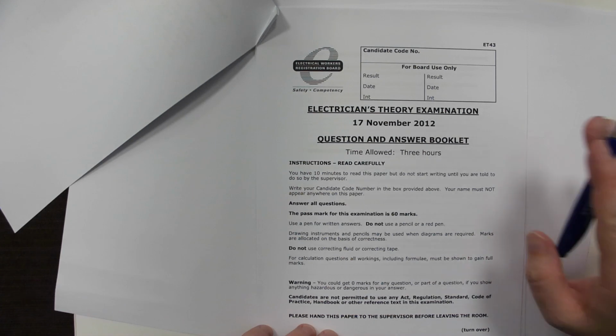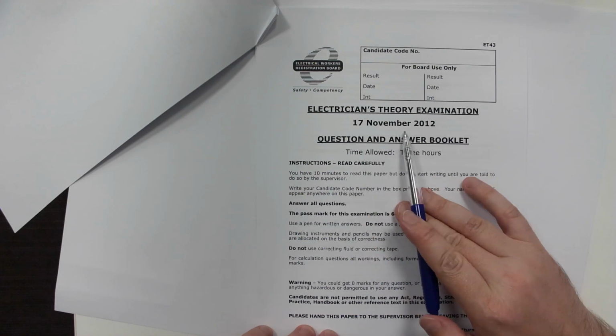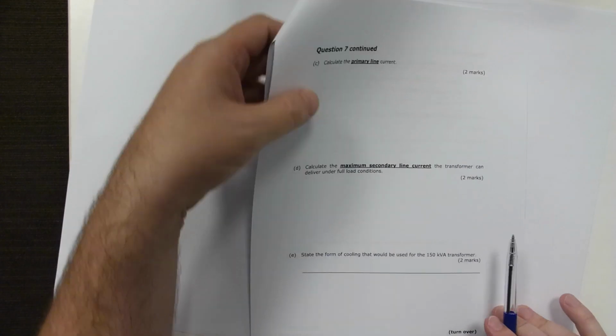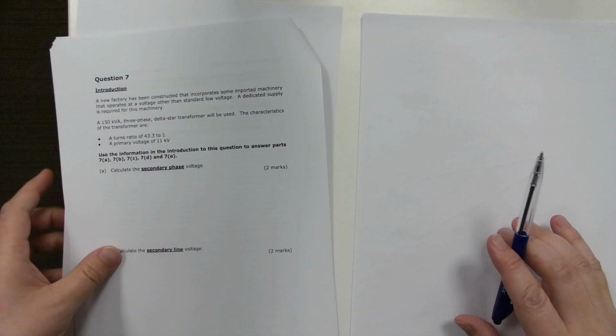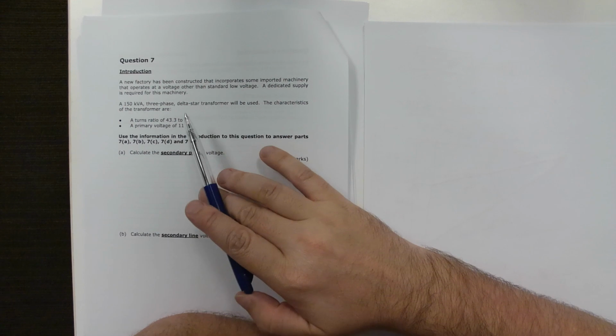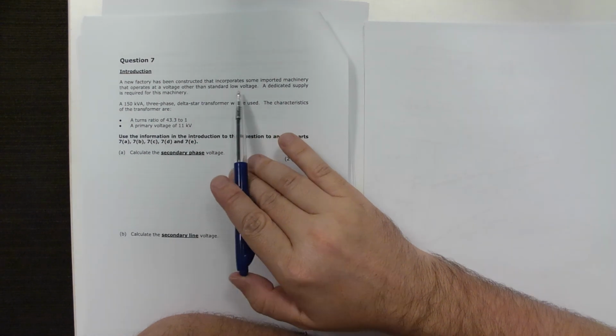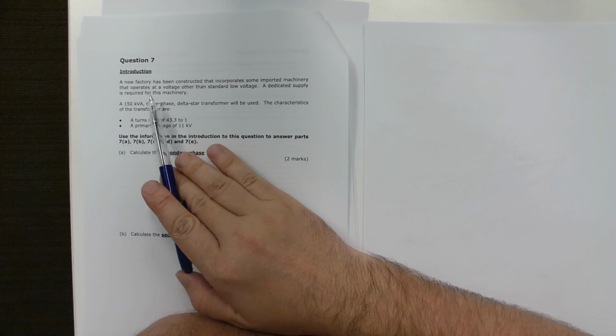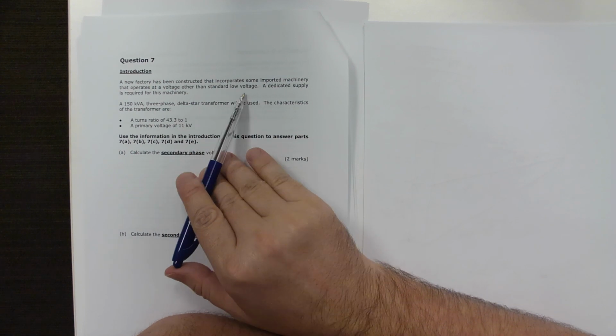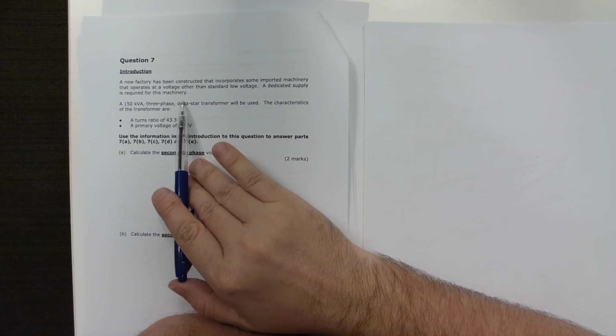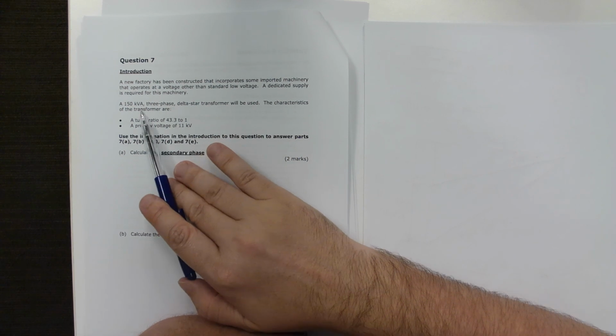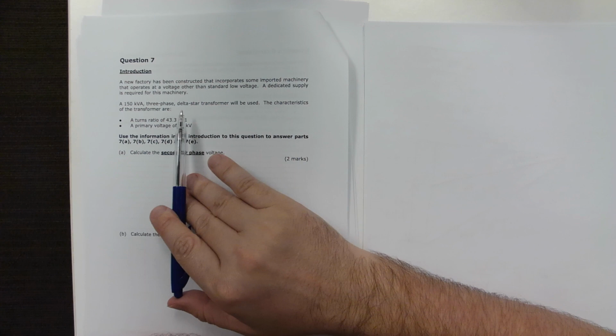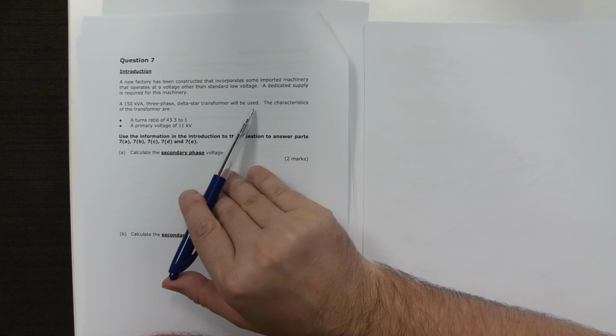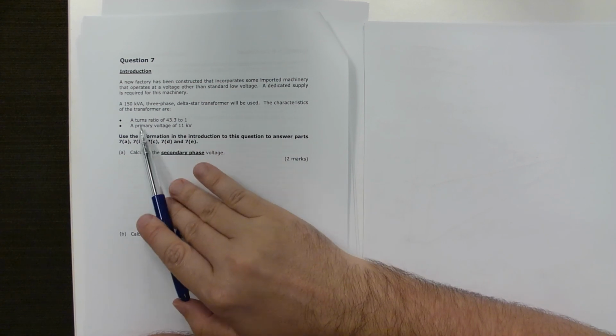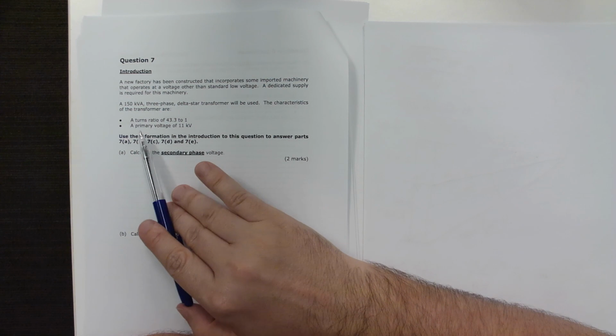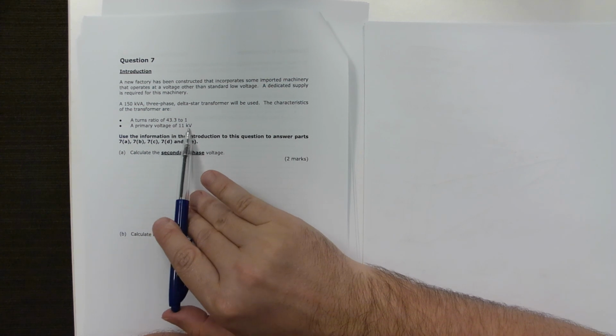Okay, so we are doing Et43, 17th of November 2012, and we are working on question 7. In question 7, a new factory has been constructed that incorporates some imported machinery that operates at a voltage other than standard low voltage. A dedicated supply is required for this machinery. A 150 kVA 3-phase delta star transformer will be used. The characteristics of the transformer are turns ratio of 43.3 to 1, primary voltage of 11 kV.